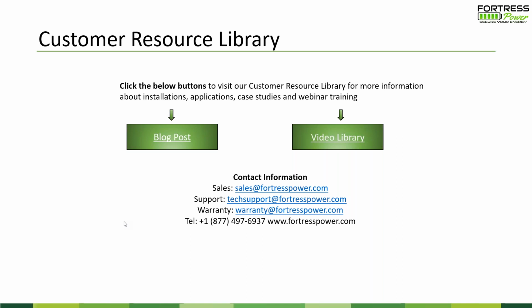Okay. So, can you just land on the bus without a breaker? Yeah, so with the eFlex, you do have a push button disconnect switch on each eFlex, and then you have the disconnect on the inverter. And so you can land just directly on the bus without a breaker and still disconnect everything from either end on all the batteries.